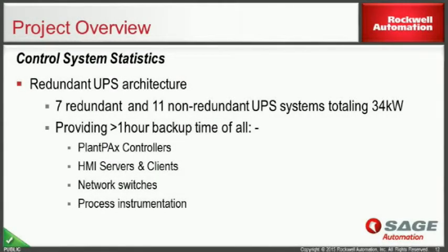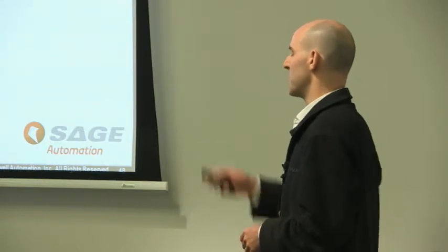And we also implemented a redundant UPS architecture, consisting of 7 redundant and 11 non-redundant UPS systems, totalling about 34 kilowatts of backup power, providing in excess of 1 hour of backup to all PlantPAx controllers, all HMI servers and clients, all network switches, and all process instrumentation across the whole facility. It was actually quite in excess of 1 hour, probably getting 2, 3, 4 hours in some areas.